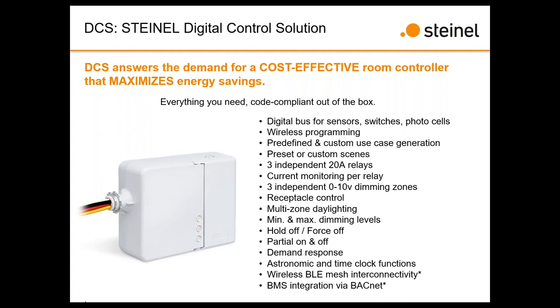We don't have pre-cut wire lengths that you need to use, and we don't have to do field terminations with 6, 8, or more small wire connections. We found from the field that that is the number one cause of pain and suffering in most Cat5 type install solutions—the terminations wind up being faulty, and commissioning agents end up spending a lot of time trying to figure out which ones are faulty and re-terminating. So we've eliminated that whole concern. At install, the contractor just simply stabs in a wire on both ends, and you're good to go. No issues.